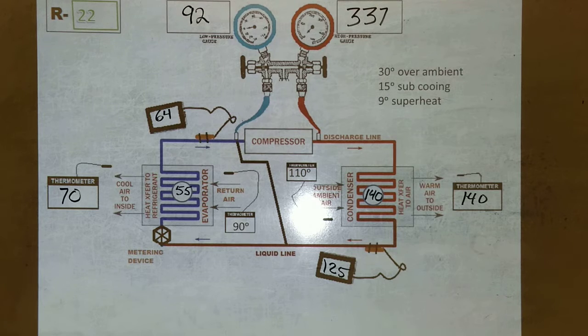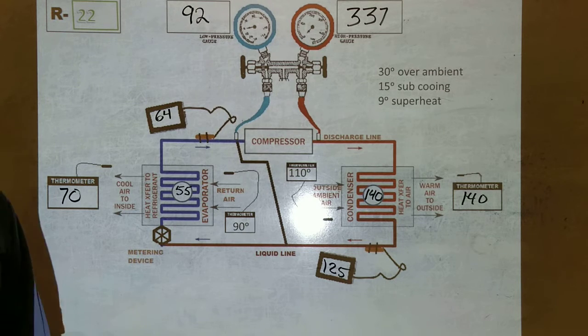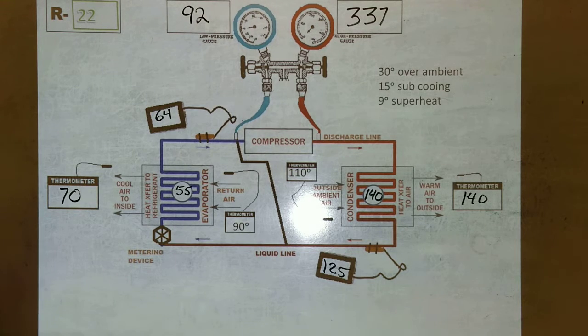If it should be 9 degrees and it's 30 degrees, I know something's wrong, something's not right. Or if it should be 9 degrees and it's a 3 degree difference, I know there's something wrong. So this is where we're going to check and we'll find out exactly what's happening with that system. We have to do this.